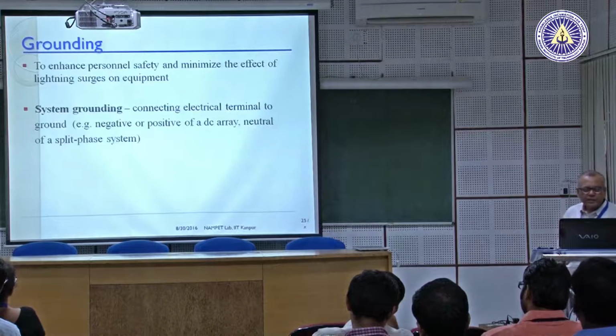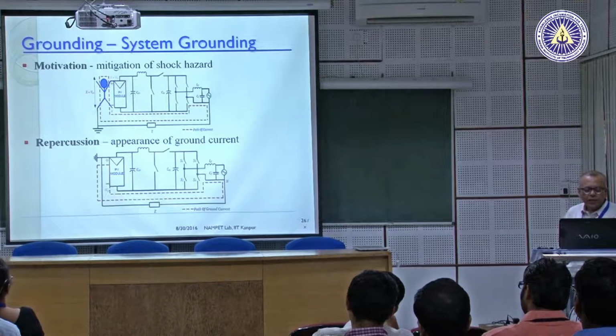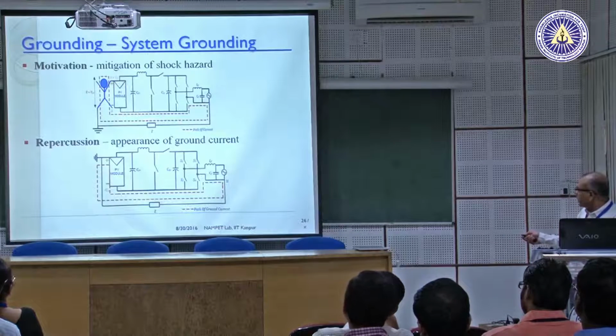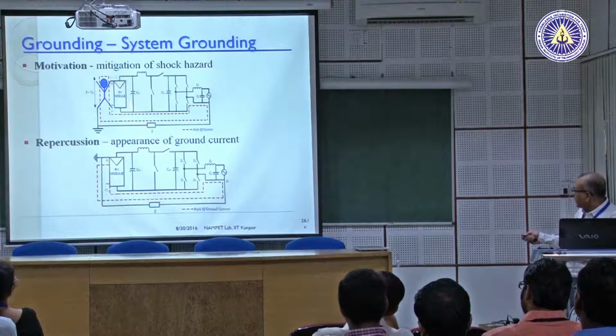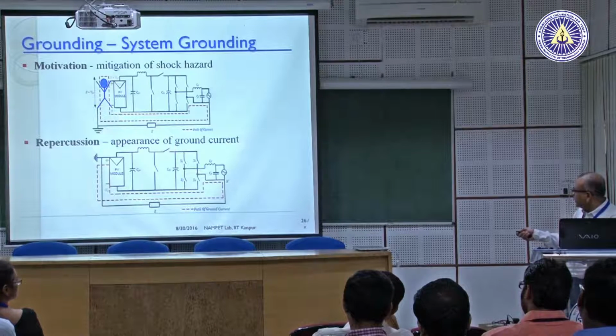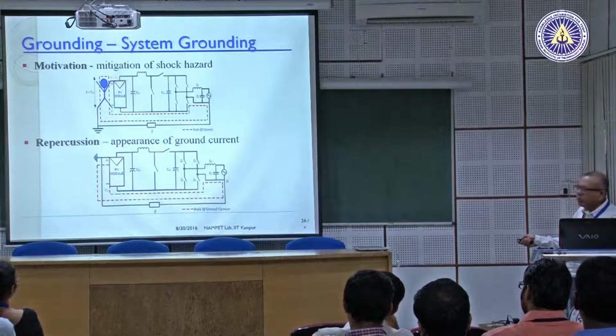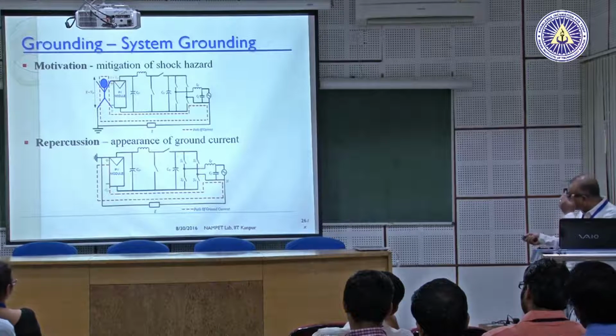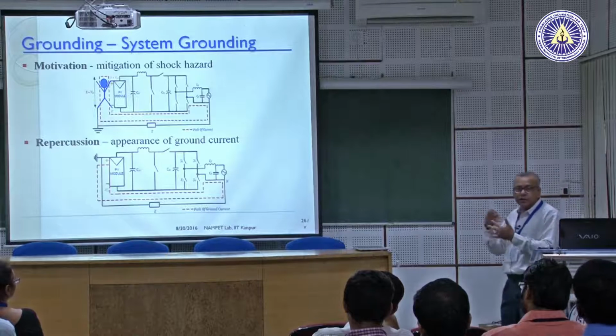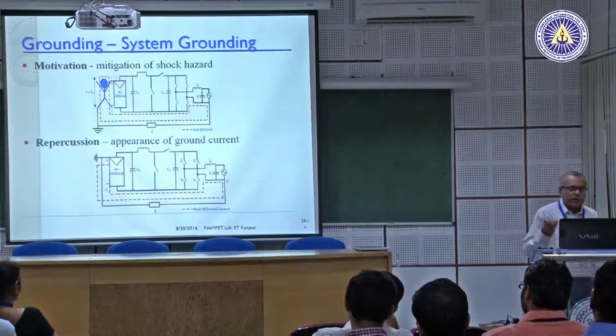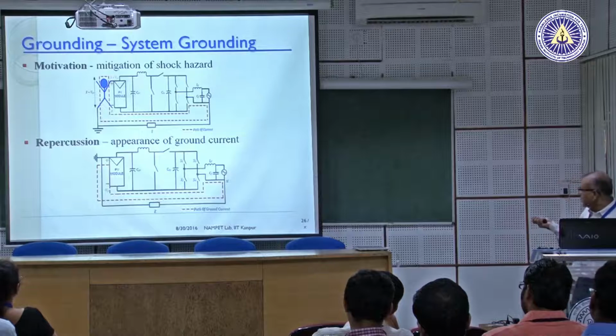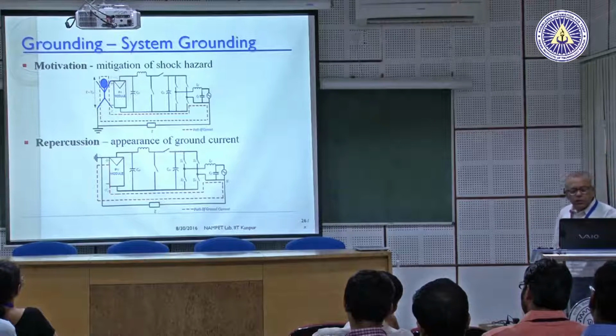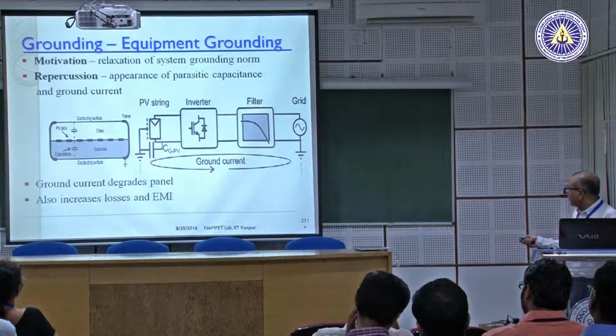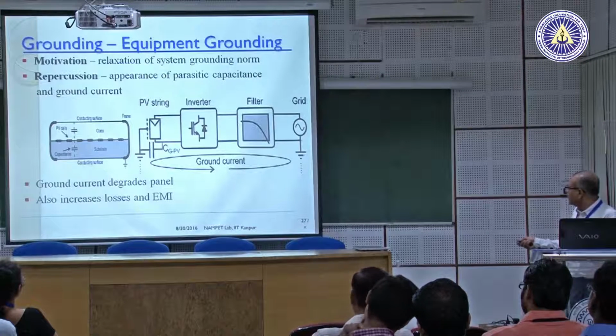The repercussion of the grounding issue is the appearance of a ground current, and it has a degradation effect on the module, number one. And of course it leads to noise pickups, usually high frequency interference. So if you have some circuits operating in the neighborhood, that is also going to get affected. So these are the effects of it.